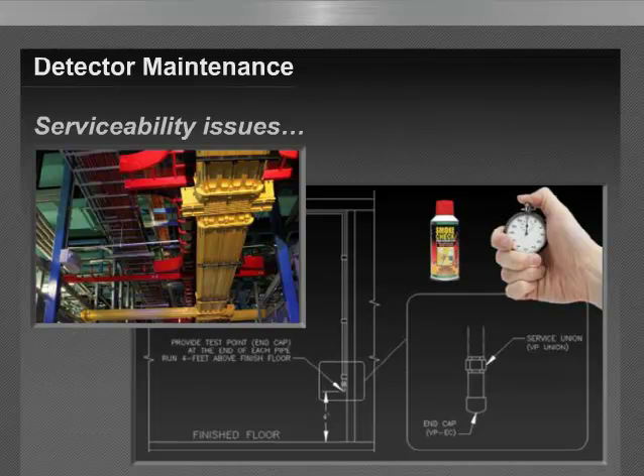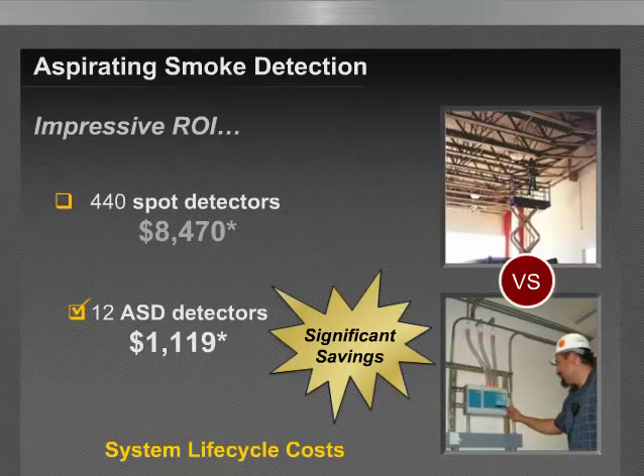So here's an example. We've taken this example to show a return on investment, and what we've done is essentially take, for instance, 12 rooms at approximately 7,000 square feet each, with the sensitivity objective of 200 square foot spacing for very early warning fire detection. And when we take that and do a comparison between spot type detection and air sampling, aspirating type detection technologies, we'll see that there's an exceptional, unsurpassed return on investment.